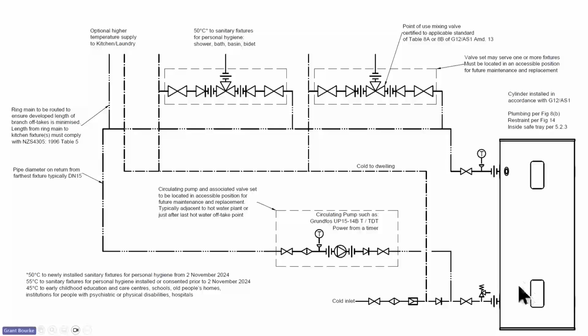So if we have a look at a hot water ring main, here's a schematic. This is in the book that'll come out, and you're welcome to contact us and we can send you CAD drawings of all these things. So let's work our way around this ring main. We're just showing a generic hot water plant. We're not worried about the hot water plant at this stage. We're just going to look at the ring main itself. So if we have a look as we come out of the ring main, we've got a couple of temperature measuring positions there.